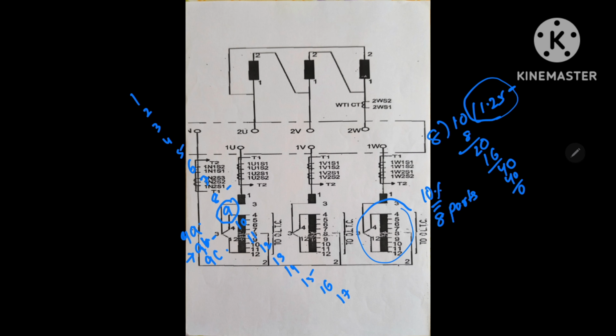So here to here is 1 plus 1.25%. So here it is 100%. And like that here it is 1 minus 1.25%. Now in the tap lowering case, when primary voltage is rising, we are reducing the tap. So here number of turns also we have to increase. So here 1.25% is each step, it will add 1.25%.